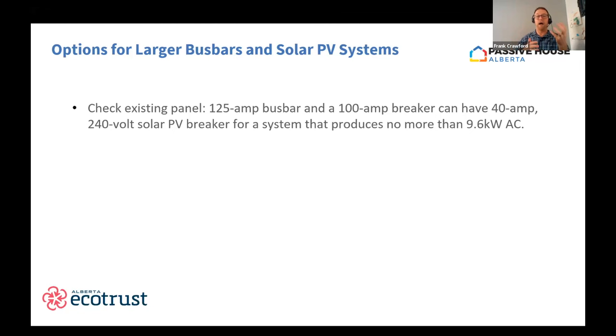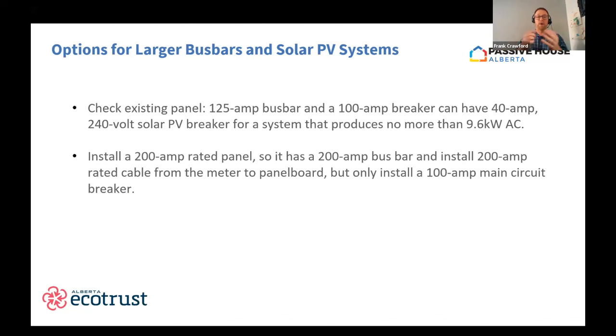The nice thing is, if you have a 125 amp bus bar, that is the size of your panel, and a 100 amp main breaker, then you can have about a 40 amp, 240 volt circuit for your PV, which means you can have a system that creates 9.6 kilowatts instantaneous AC power, which is a pretty big system. If you still want a bigger system, then you could pull out the panel and put in a 200 amp rated panel, which means you have a 200 amp bus bar. And then just for future proofing, I would still install 200 amp cable from your panel to your electrical meter, but then you only install that 100 amp main breaker, which means you have 100 amp service, because that way you can now have up to a 28.8 kilowatt AC solar array, which is far more than you'd ever need.